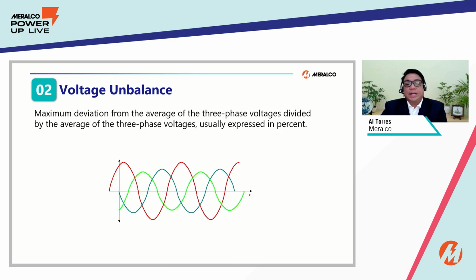Next is voltage imbalance. So voltage imbalance is critical for three-phase loads. As defined by the Philippine Distribution Code, voltage imbalance is the maximum deviation from the average of three-phase voltages divided by the average of three-phase voltages, expressed in percent. So high voltage imbalance may result in excessive heating on motor windings. And based on the Philippine Distribution Code, the maximum voltage imbalance should be below 2.5% at the point of connection.